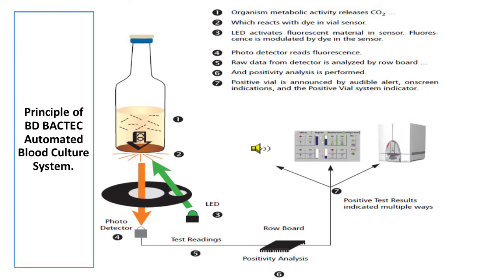A dye in the sensor at the bottom of the culture bottles reacts with CO2, modulating the amount of light absorbed by a fluorescent material in the sensor. The instrument's photo detectors measure the level of fluorescence, which corresponds to the amount of CO2 released by the organisms. The measurement is then interpreted by the system according to pre-programmed positivity algorithms.